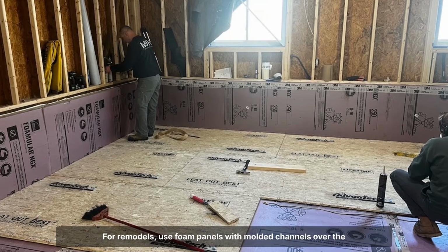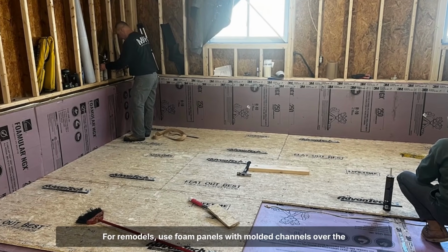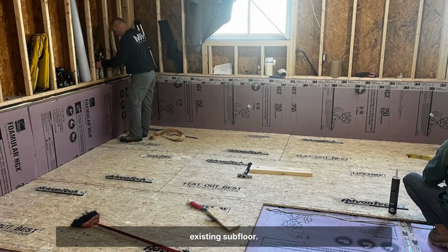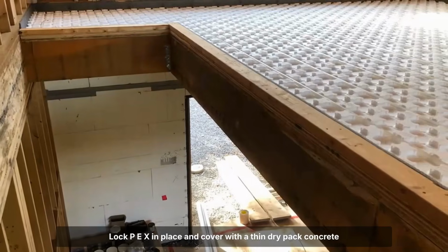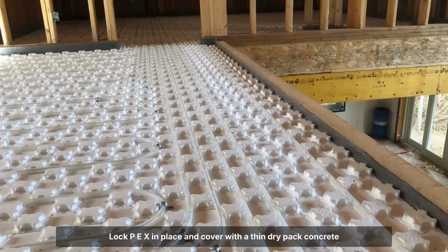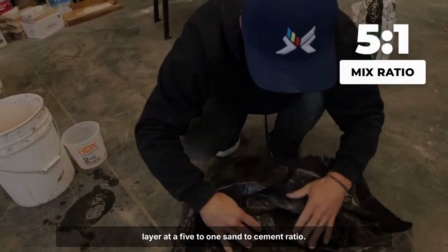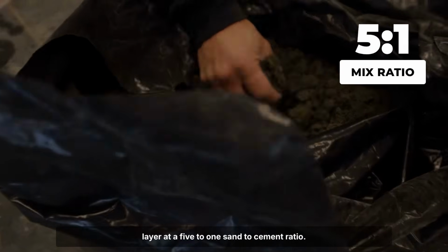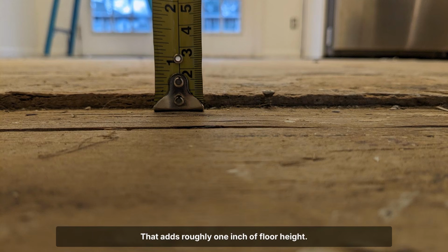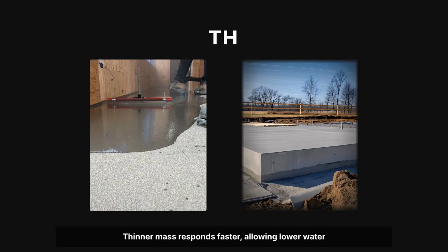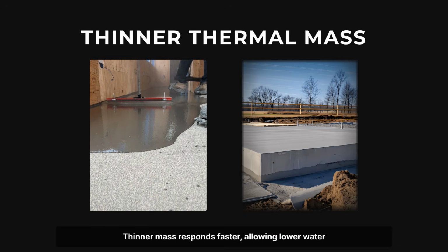For remodels, use foam panels with molded channels over the existing subfloor. Lock PEX in place and cover with a thin, dry pack concrete layer at a 5:1 sand to cement ratio. That adds roughly 1 inch of floor height. Thinner mass responds faster, allowing lower water temperatures and reduced energy costs.